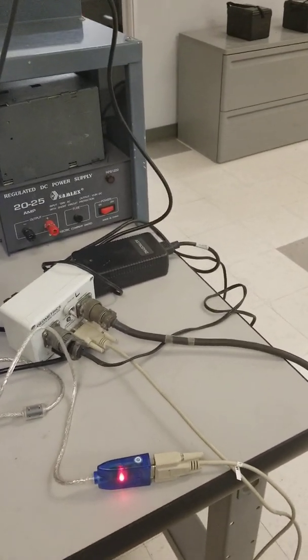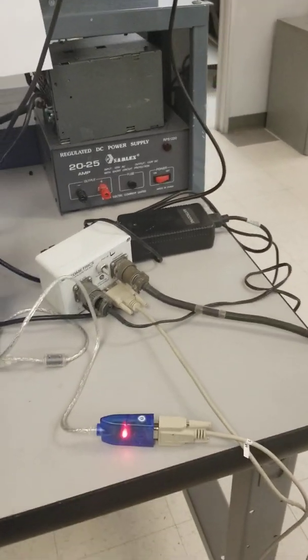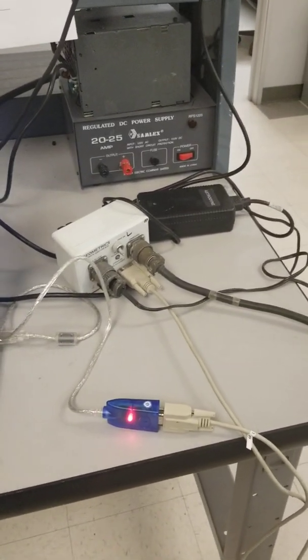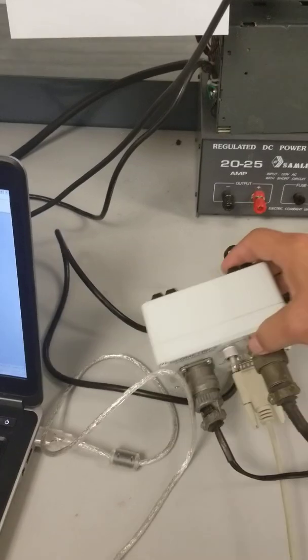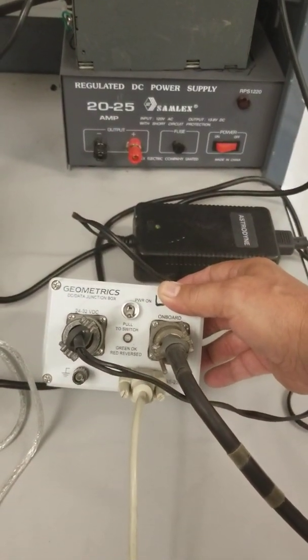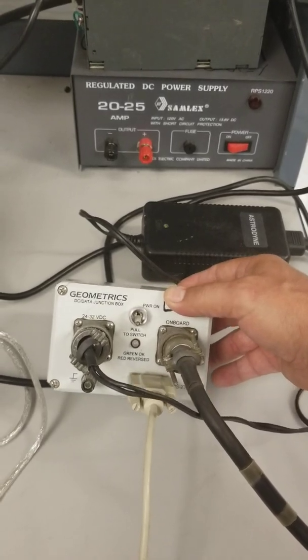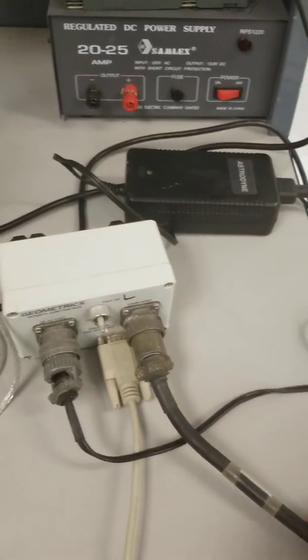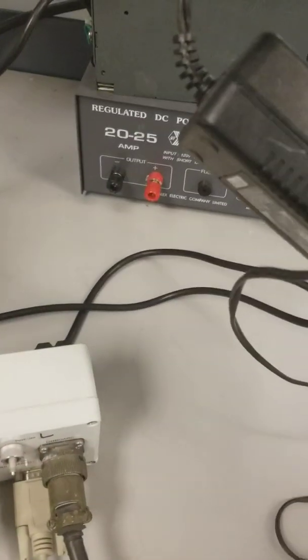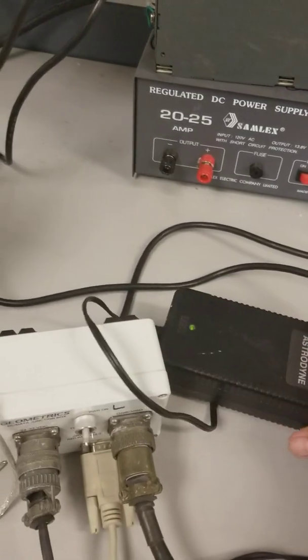Okay, so let's talk a little bit about the connections of your equipment. To do the diagnostic survey, you simply need your DC data junction box as shown, the power cable right here, which we have connected to our small supply, and our small supply is just plugged into our outlet here.